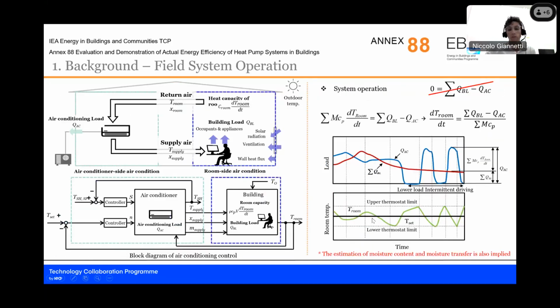Okay. So I think we can first start describing how this system operates in a building. In the case of an air conditioner, we can imagine how this unit interacts with the indoor environment by its own native control, so the control system that is installed inside the unit and that senses, through the thermostat, the variation of the indoor temperature and tries to operate the system to meet the set temperature that we control with our remote control, or that is controlled centrally by a central system.